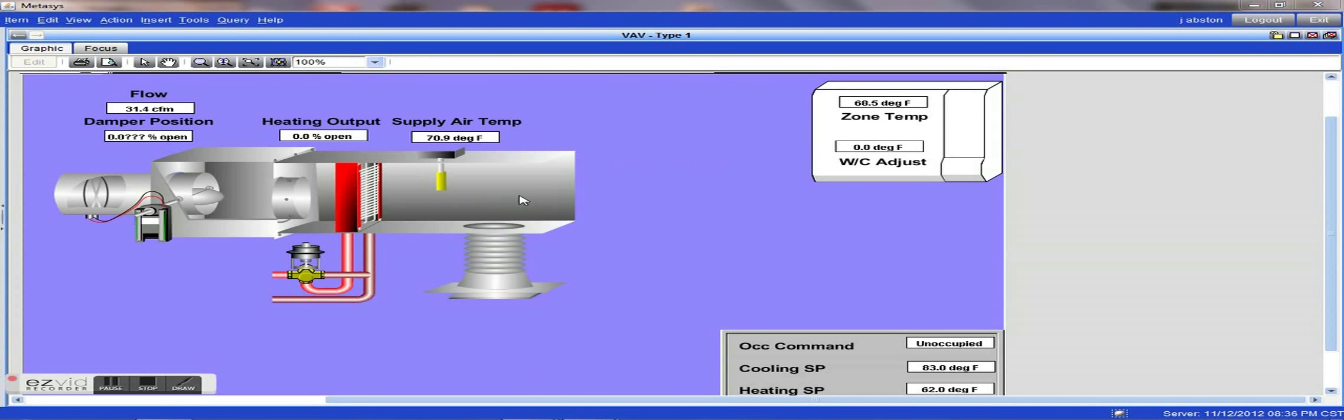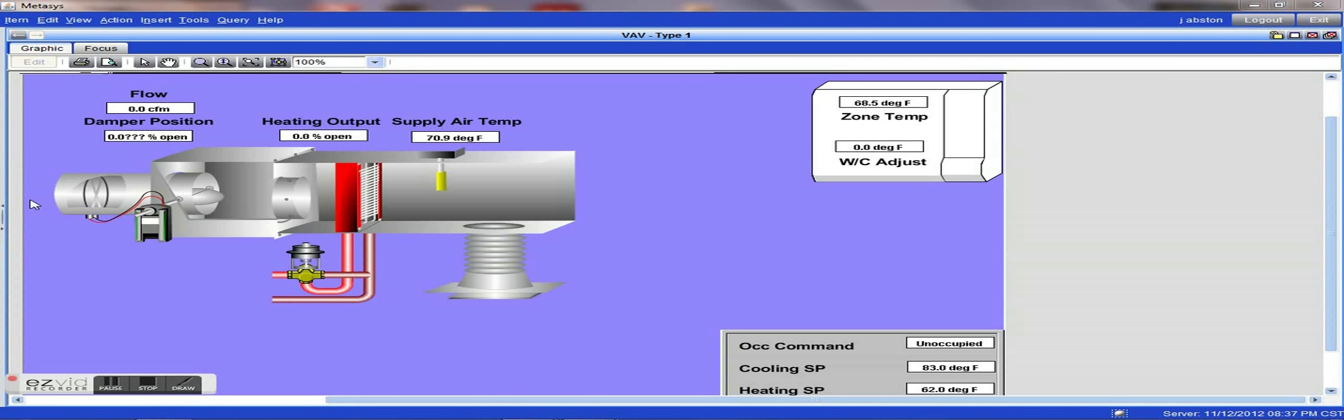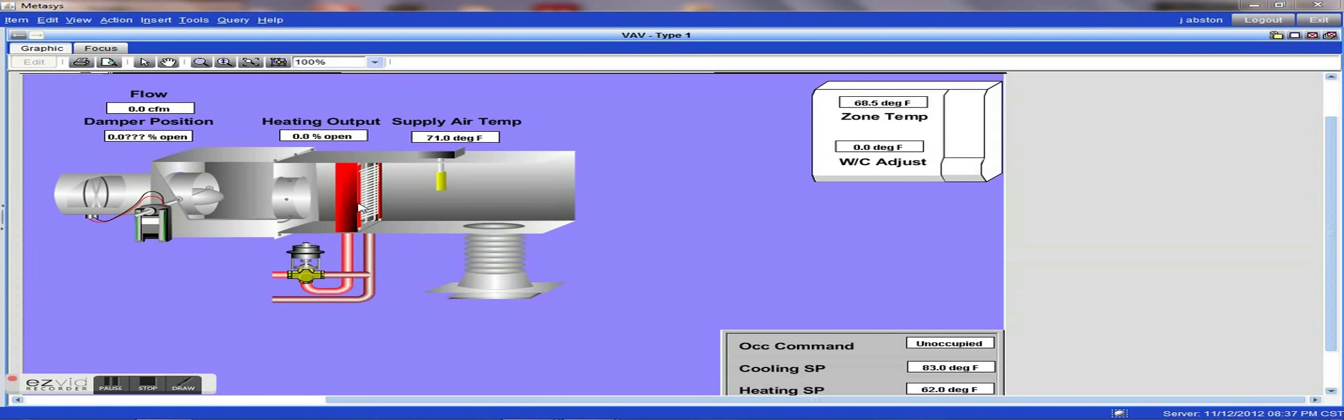One little tip that will be very helpful to you in the winter time, especially when your system is under the most load for heating, is to increase the discharge temperature of your air handler to a point where you still maintain effective cooling. However, you help to unload the individual zone controller and give it just a little bit of a boost as far as assisting it in heating.